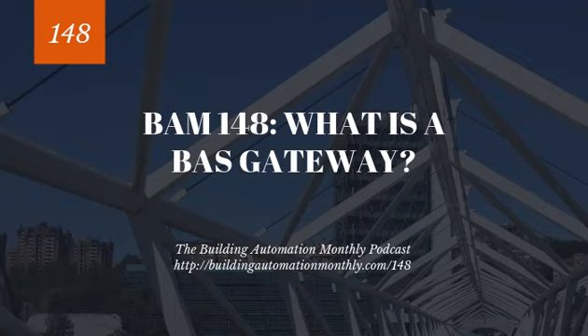Now, I realize for the past 5 minutes I've gone super uber geek on you, and you may be feeling a little overwhelmed. So here's the Cliff Notes. There are 2 types of gateways that we focused on in this episode, physical and protocol gateways. Physical gateways are almost always used when using a protocol gateway, and they are one and the same, because in order for protocol gateways to switch between protocols, they often have to switch between physical media. Protocol gateways are actually really easy to configure. You just need to follow a 4-step process of making sure what gateway you're using, making sure you've covered the physical requirements, the protocol requirements, and then testing the installation and configuration of the gateway.